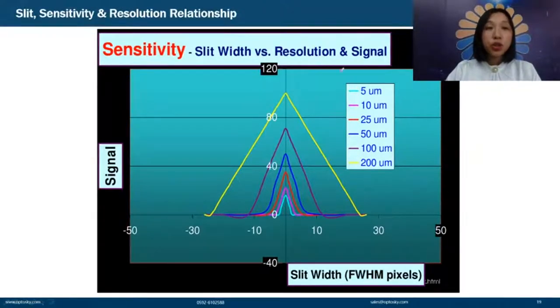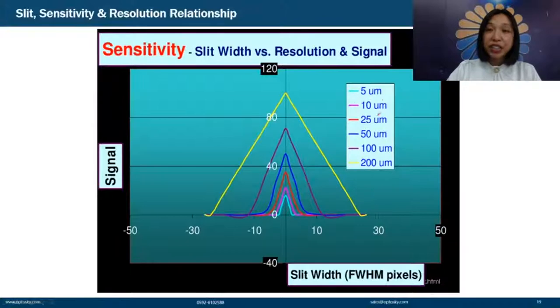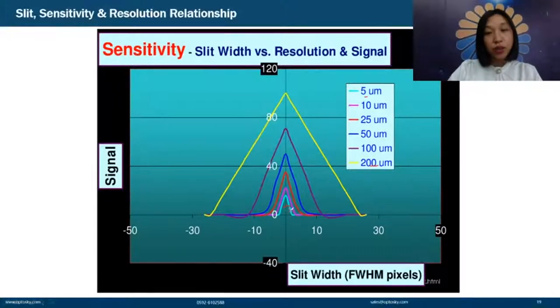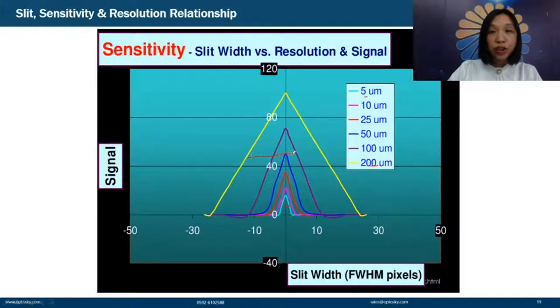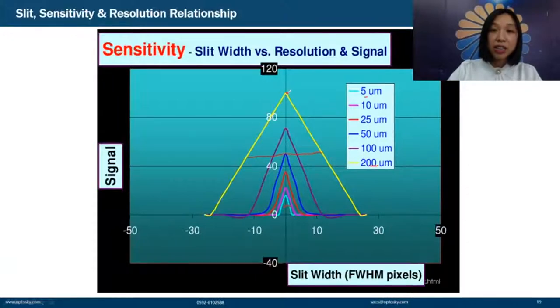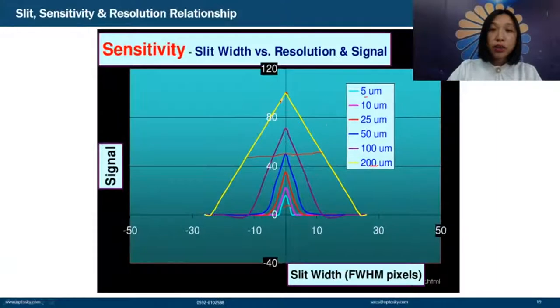This graph vividly shows the relationship between slit width, sensitivity, and resolution. Different colors indicate different slit sizes — for example, 5 µm and 200 µm. With a 5 µm slit, the peak is very narrow, so resolution is highest. With 200 µm, the peak is much broader — poorer resolution. However, signal intensity is highest with the wider slit. This clearly illustrates the trade-off between sensitivity and resolution.